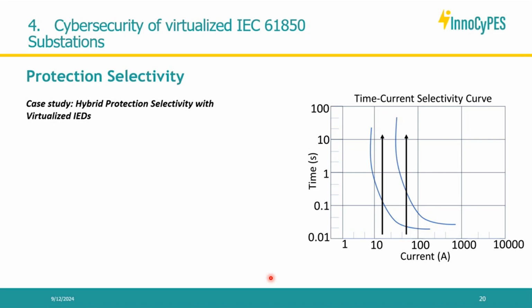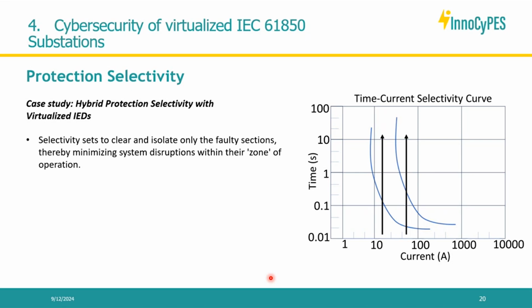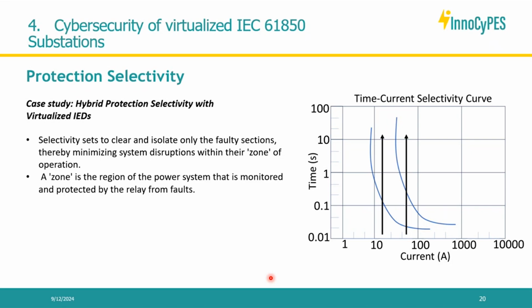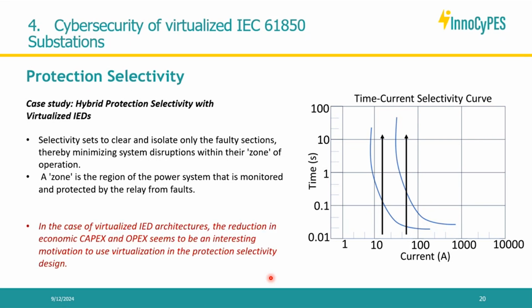Now I'm going to talk about the case study we did for the tests on the test bed. We used a case study on protection selectivity, because as I explained, we had two IEDs: one virtual running overcurrent protection, and one physical running distance protection. So we resorted to a concept called protection selectivity, which means protecting a certain zone on the grid by isolating and disrupting the minimum possible zone, using this protection coordination concept.